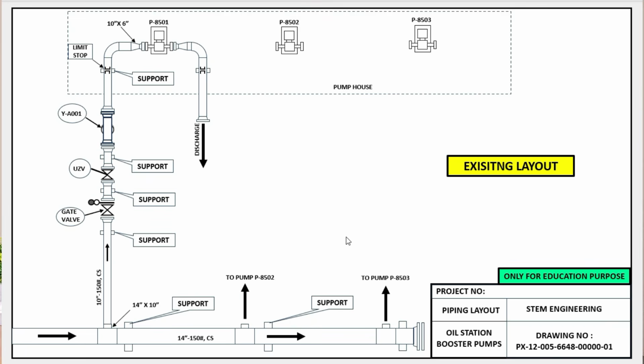Now I will show you the piping layout for the same arrangement. The same arrangement has been typically reflected here, but for the sake of this video, I have only represented the suction line. I have not represented the discharge line to avoid contractual terms. So let me show you the arrangement over here, which is exactly the same as the P&ID. You can read out the piping layout that starts from the isolation valve, and then the spectacle blind, and then the control valve, and then the strainer, and then it goes to the pump suction. It is exactly meeting the P&ID.